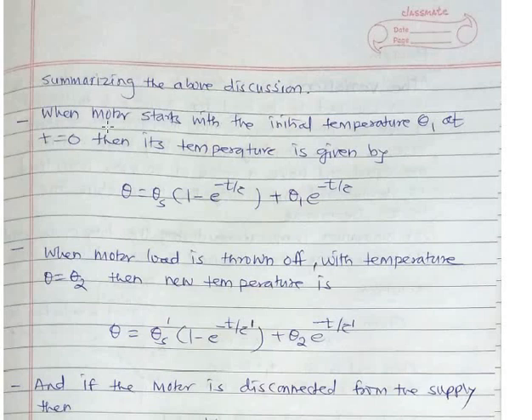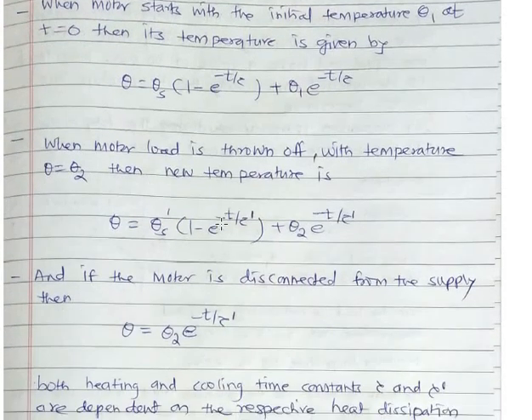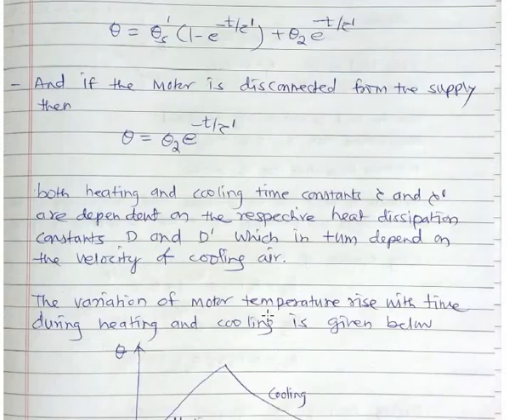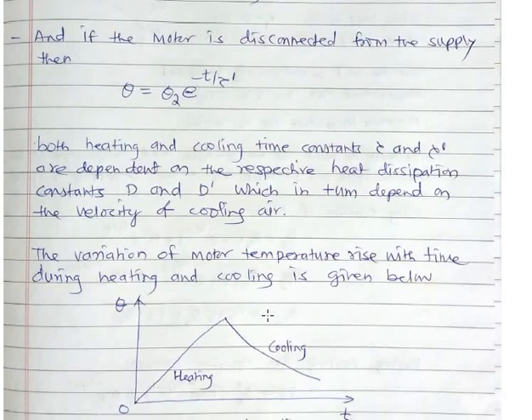Summarizing the above discussion: when the motor starts with initial temperature theta 1 at T equals 0, its temperature is given by the heating expression. When the motor load is thrown off with temperature theta equals theta 2, the new temperature is given by the cooling expression. If the motor is disconnected from the supply, theta equals theta 2·e raised to minus T upon tau dash. Both heating and cooling time constants, tau and tau dash, are dependent on the respective heat dissipation constants D and D dash, which in turn depend on the velocity of cooling air.